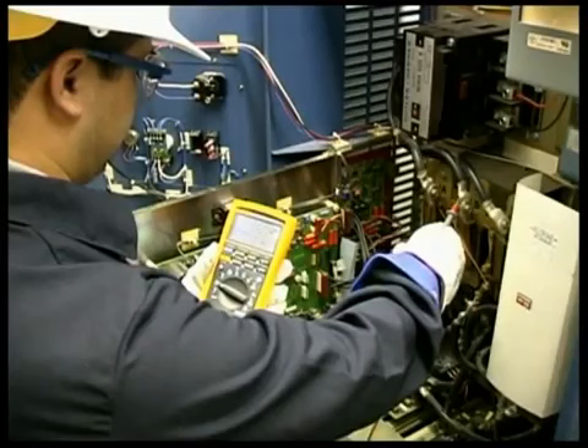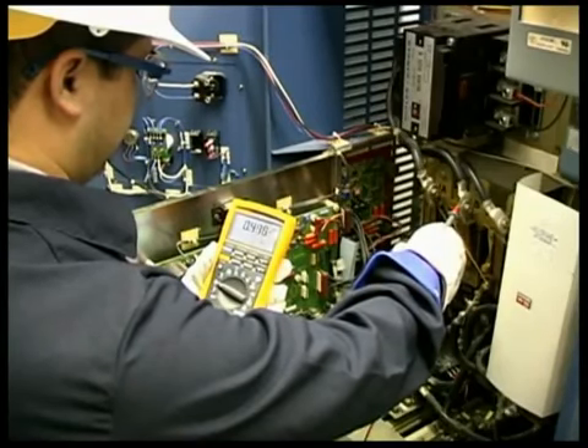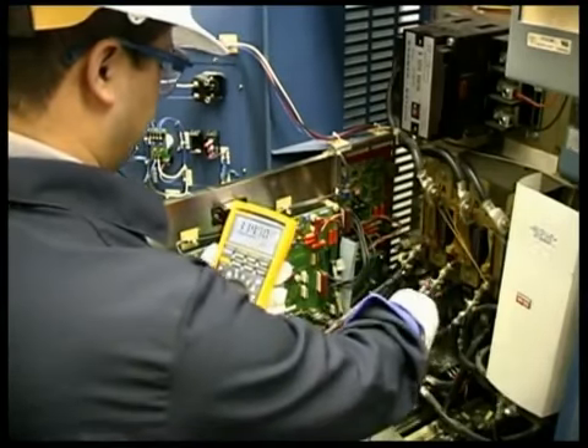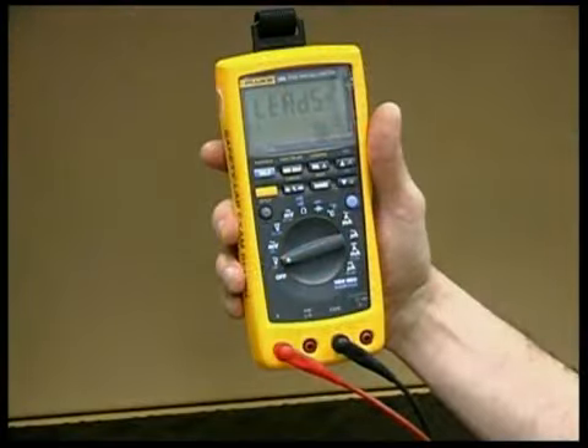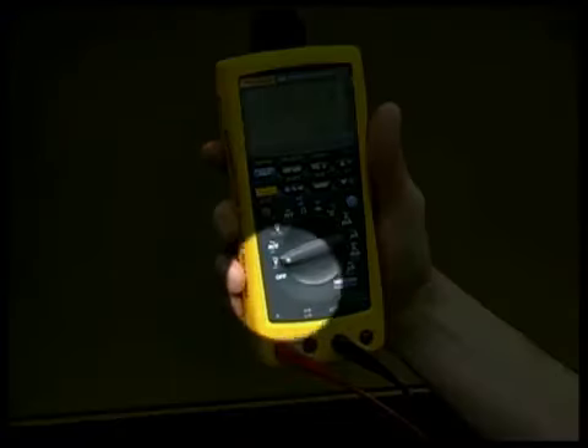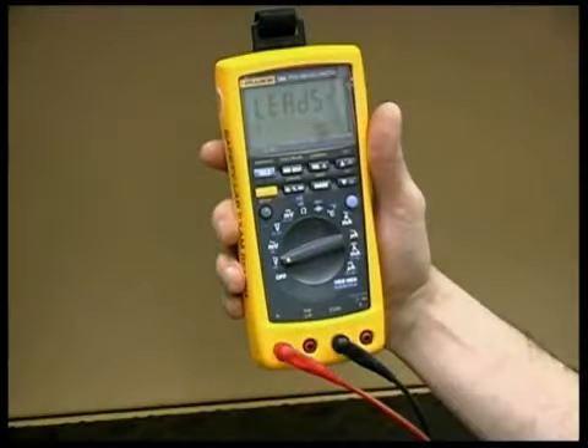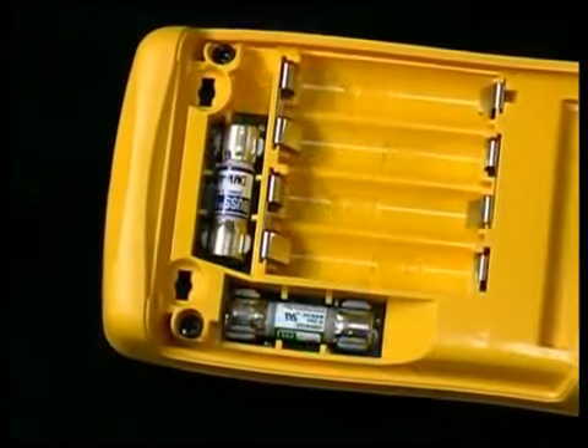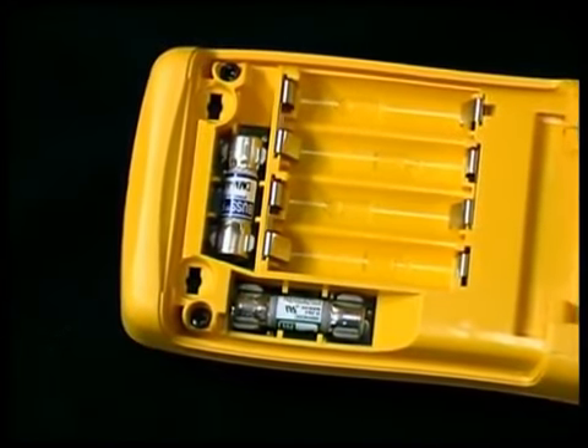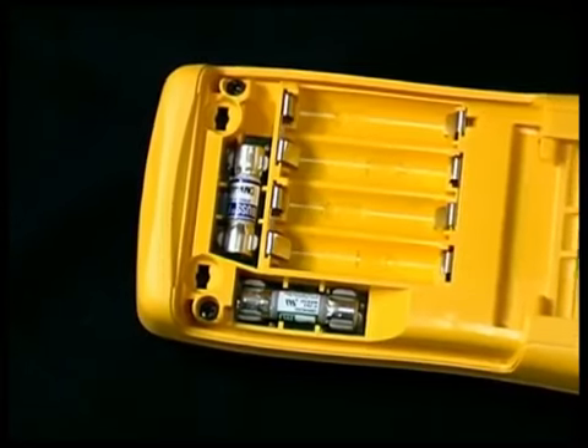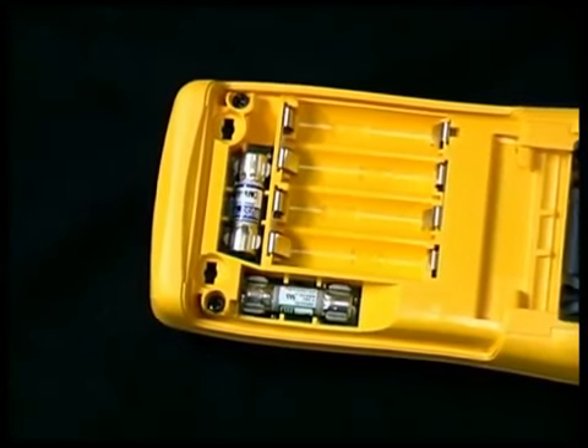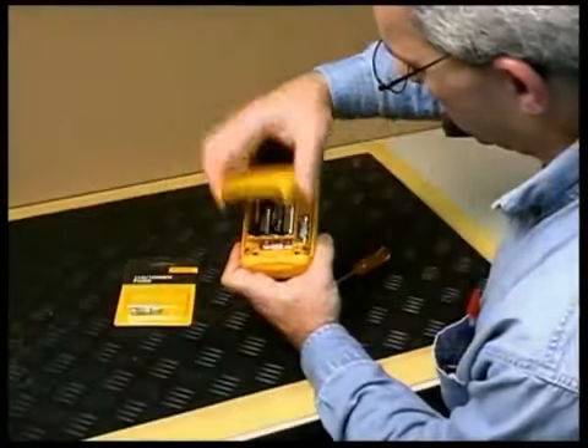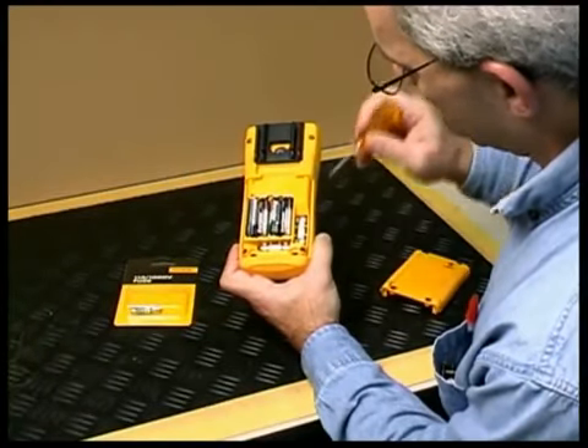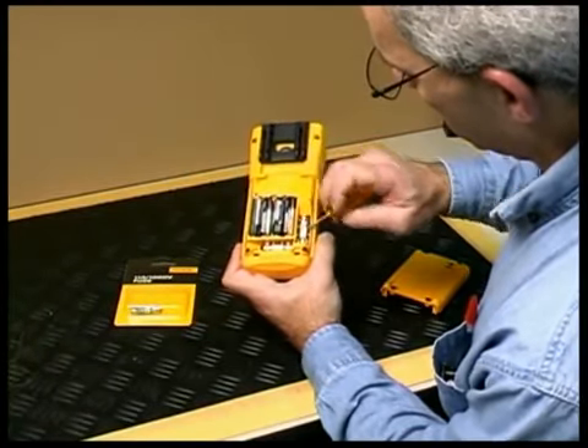Transients aren't the only source of arc flash hazard. One of the most common misuses of multimeters can cause a similar chain of events. If the user leaves the leads in the amp's inputs and then accidentally connects the meter to a voltage source, he has just created a short through the meter. That's why the amp's terminals must be protected by fuses. These fuses may be the only protection against a potential disaster. If the meter is fused correctly, the result is a damaged fuse, which is a small price to pay.